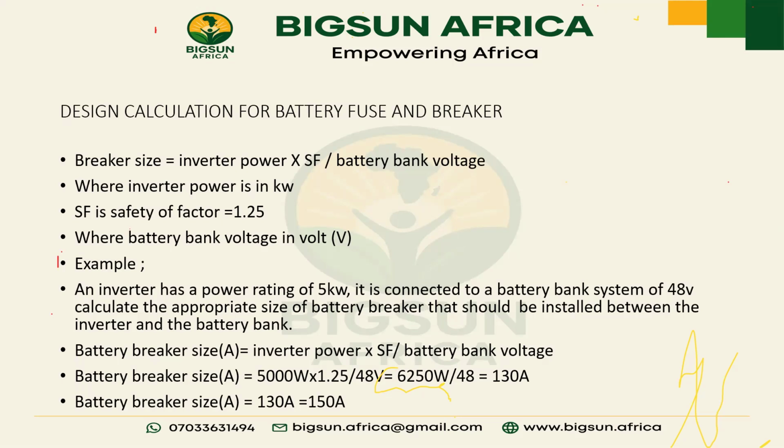Yeah. But charging the battery requires what? DC. So the AC that is still coming in from NEPA will be converted to DC. And a 5 kVA inverter cannot consume or send more current than it is designed to. So this calculation we are doing is based on that 5 kVA. This is how much current it can draw at a time.